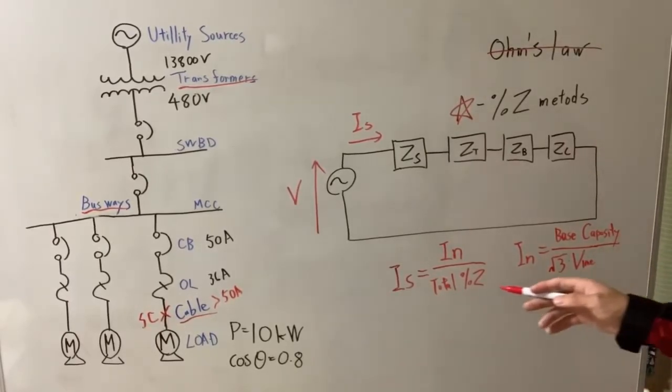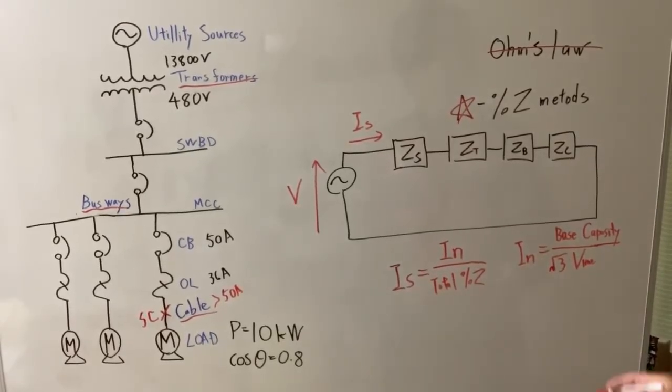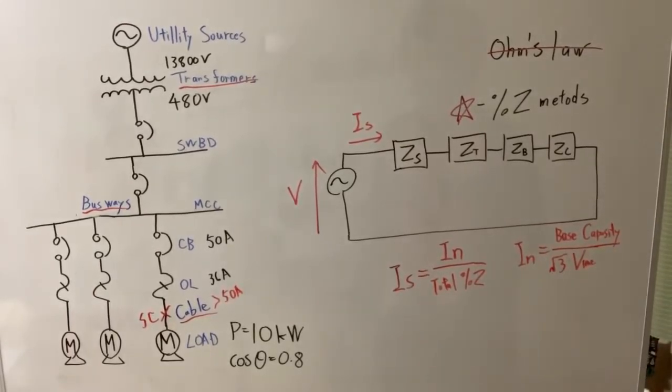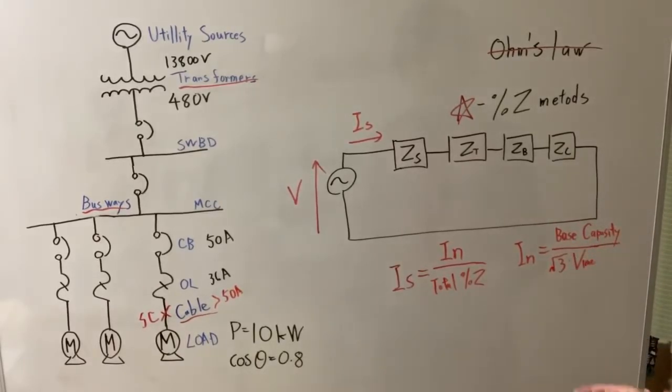The base line voltage is the voltage at the point of short circuit occurred. So in this case, 480 volt. So the base capacity is arbitrary, you know, it's up to you. You can select it. And once you set this base capacity, no matter how many transformers you have, you don't need to convert each one. You know, just apply this formula.